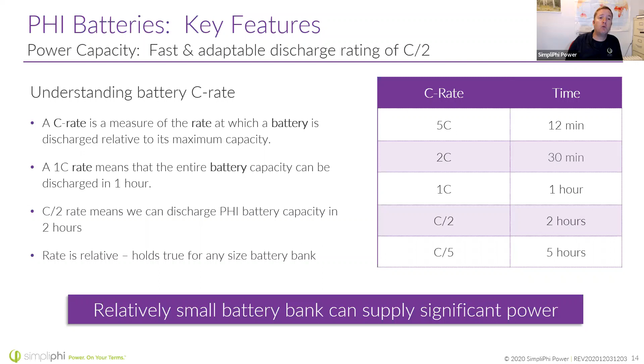Also use a generator at full capacity, not run it at an idle rate. Our batteries have a C/2 rate, which means that if you have a 3.8 kilowatt hour battery, you can charge or discharge that battery at 1.9 kilowatts.